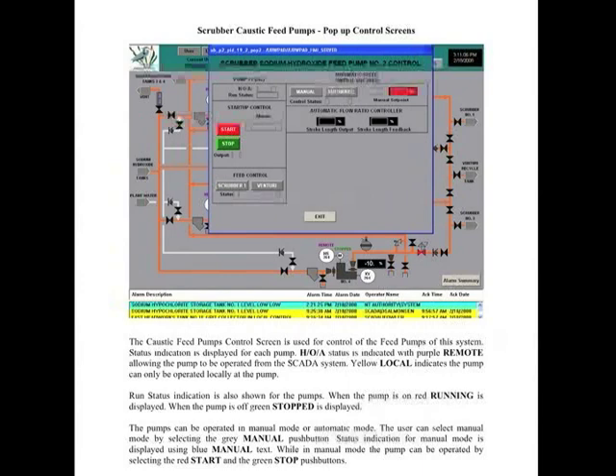You also have the ability to run this by flow. You basically set a set point that says, I want 5 gallons per hour pumping in. You put in 5 and the system takes care of speeding up the pump in order to maintain 5 gallons per hour. Though that's excessive because I think these pumps only do 0.5 gallons per hour, so you'll never make it otherwise.